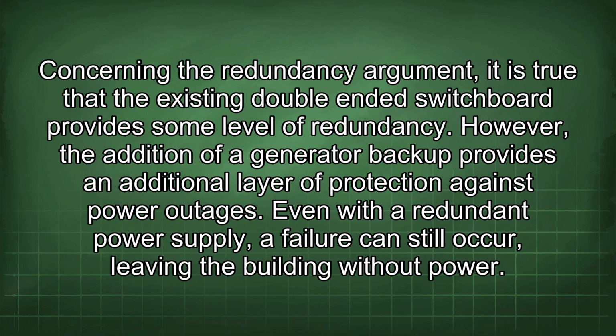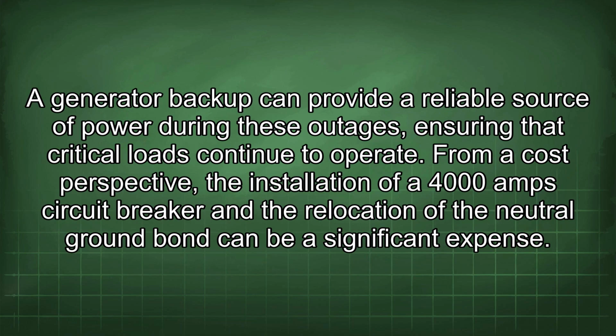grid. Concerning the redundancy argument, it is true that the existing double-ended switchboard provides some level of redundancy. However, the addition of a generator backup provides an additional layer of protection against power outages. Even with a redundant power supply, a failure can still occur, leaving the building without power. A generator backup can provide a reliable source of power during these outages, ensuring that critical loads continue to operate.